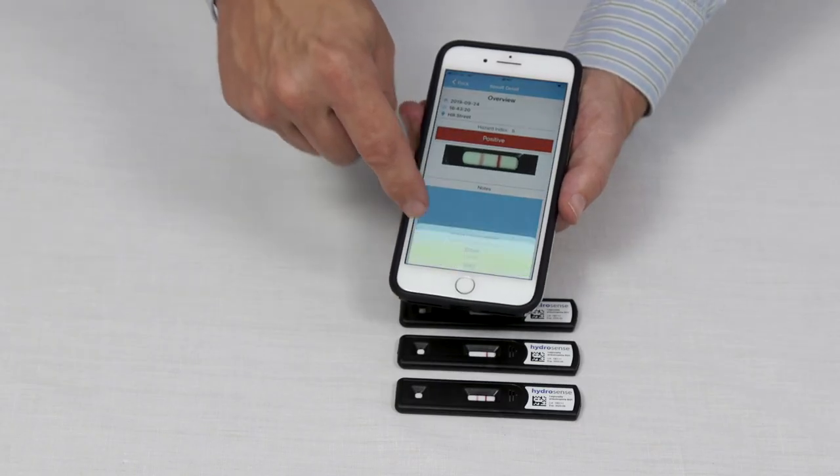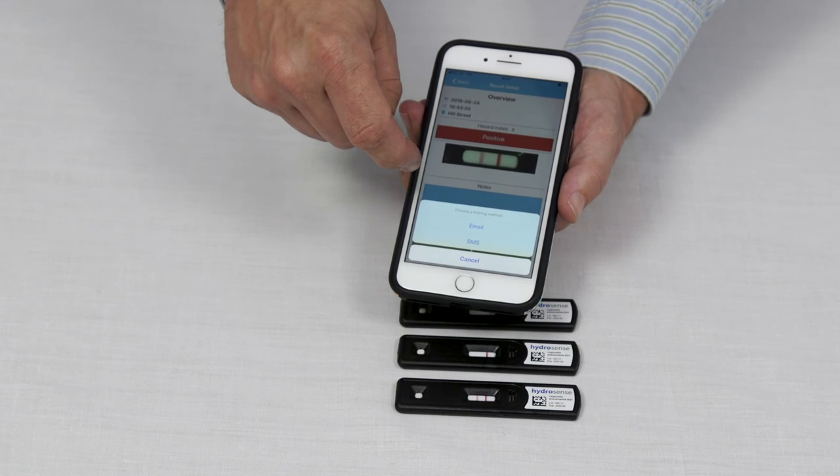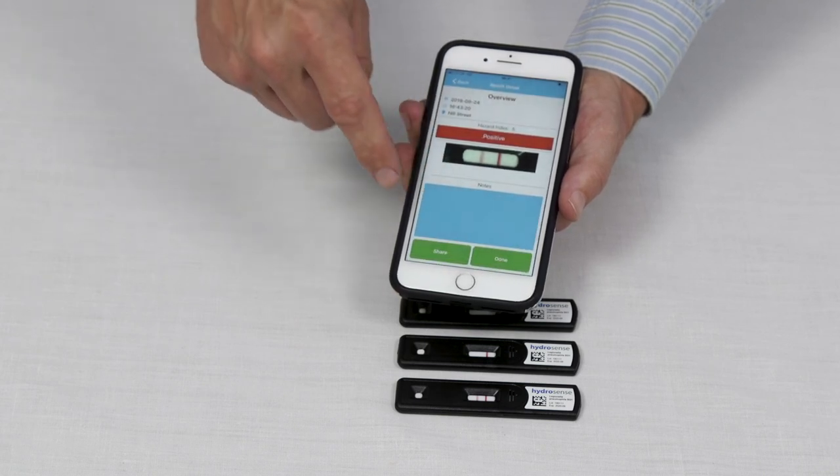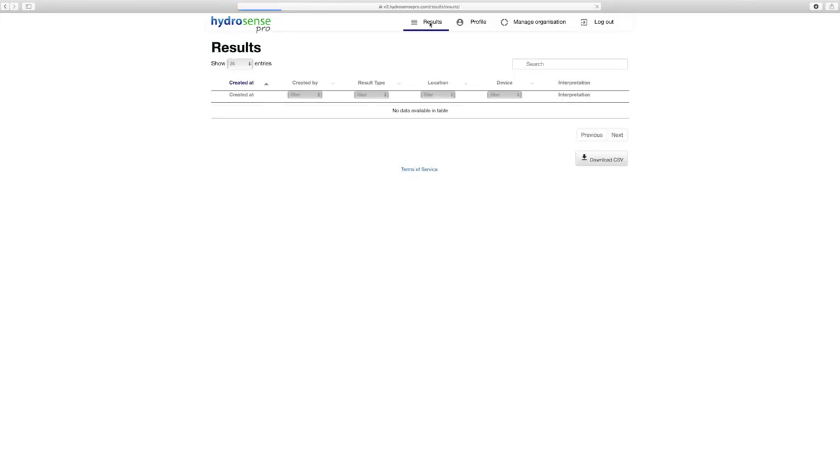The positive result indicates that Legionella pneumophila serogroup 1 has been detected in the sample. Results can be shared via email or SMS, or results are also automatically uploaded to the HydroSense Pro portal at HydroSensePro.com.